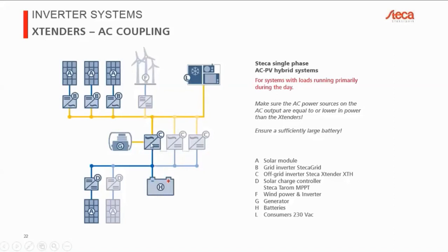Or you can have an external separate source of energy, so you can connect on the DC side a standard charge controller, MPPT or not, regardless, directly from PV to the battery so that you can recharge the battery even if all of this AC side has shut down. Or the third option is you use a generator to inject into the battery. If you do use a generator, you need to make sure that you turn off the grid inverters while the generator is running. This is to avoid any possible backfeeding of the generator into the grid inverters. Under normal circumstances, backfeeding does not happen because the Xtender will simply rectify that energy and pump it into the battery. But just to be sure, we strongly recommend to switch off the grid inverters while the generator is running.